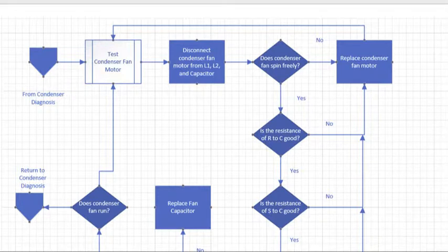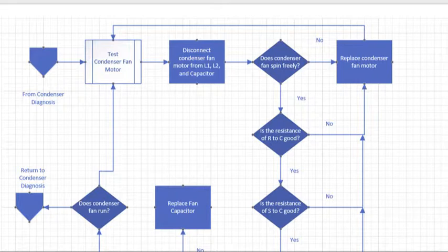Next, check if the condenser fan spins freely. Part of the reason why I want you to disconnect this before you test the spinning of the motor is this way you never have a chance of accidentally energizing that motor while your fingers are in it. If the condenser fan does not spin freely, just replace the motor.